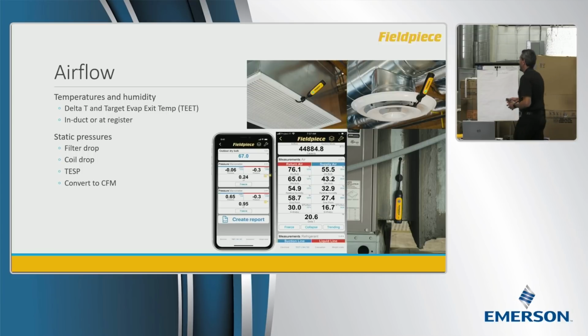Okay? Now, to take a total external static pressure test, it's important to know where to hook up the measurements. So in this particular piece of equipment, we've got a furnace and an air conditioning vertical, right? All in one. Now, what we don't do to take a total external static pressure measurement is include the heat exchanger, the blower, and the evap coil. That's not how you properly take a total external static pressure. What the manufacturer specifies is the pressure differential before and after the blower and the heat exchanger. That's it. That's what they specify as total external static pressure.